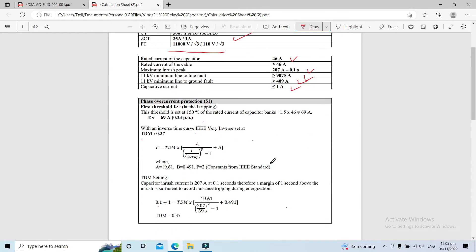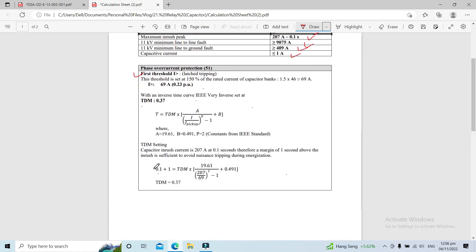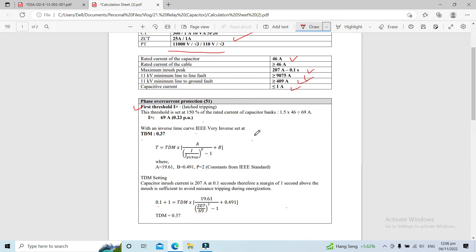Now let's proceed to our calculation for phase overcurrent protection, ANSI 51 relay. We will have two thresholds. For the first threshold, the pickup current has to be 150% of the rated current of the capacitor bank. So we have 1.5 times 46 ampere, giving a pickup current set at 69 ampere, or 0.23 per unit.